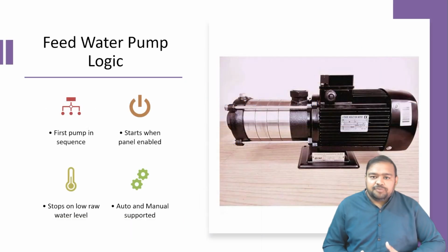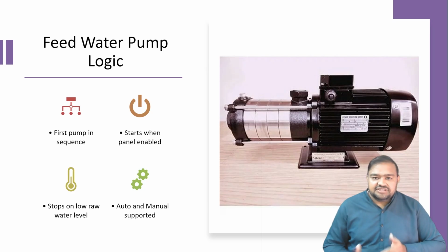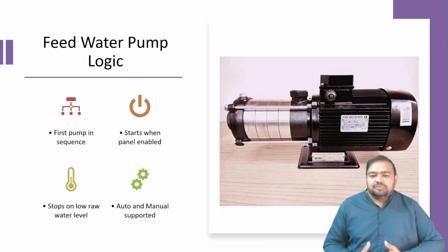The feed water pump is the first pump in the sequence in auto mode. The feed pump starts when the panel is enabled. It supplies water to the RO system. It stops immediately if the raw water level becomes low. In manual mode, the operator can start the pump, but low level protection and overload protection remain active. This pump acts as the base condition for the entire system.